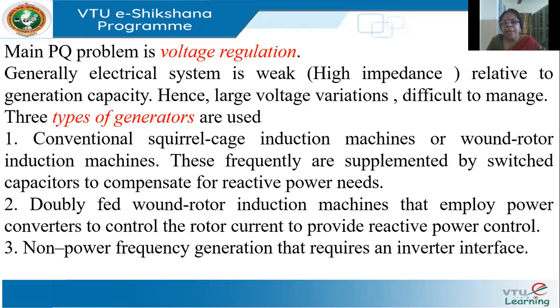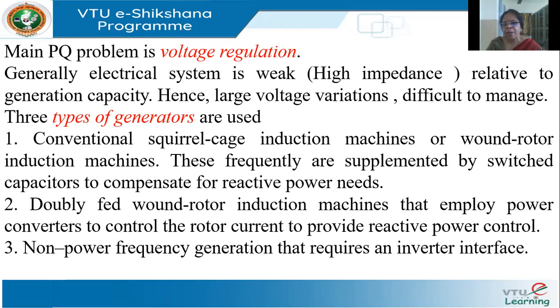Since it's a prime mover, a generator is needed with it. The commonly used generators with wind turbines are conventional squirrel cage induction machines or wound rotor machines — three-phase squirrel cage or wound rotor. These machines require reactive power since the induction machine acts as a generator, so capacitors may be provided to supply sufficient reactive power. Otherwise, it may draw reactive power from the grid, causing the voltage at that point to fall.